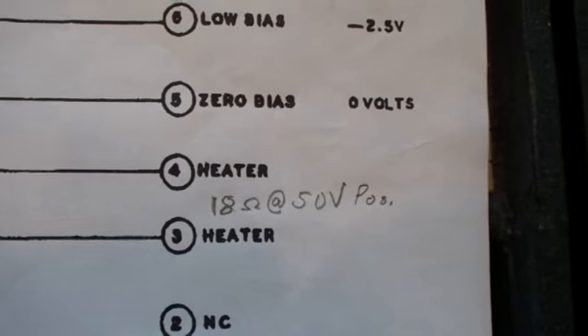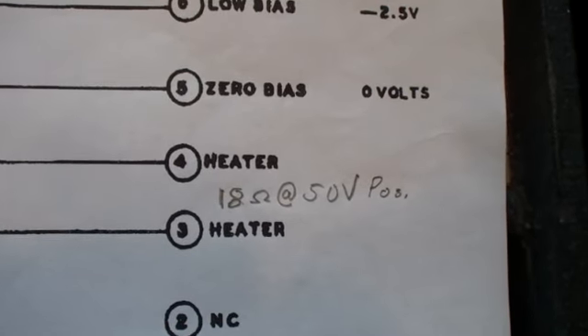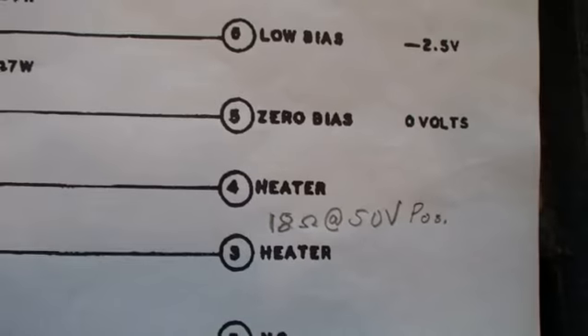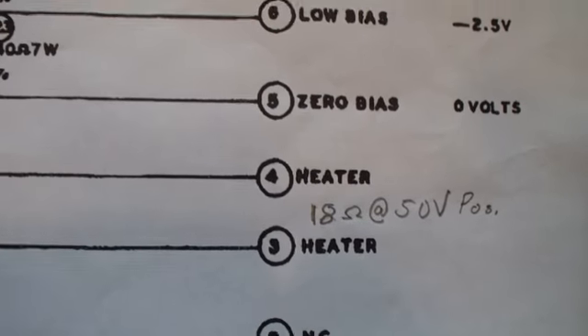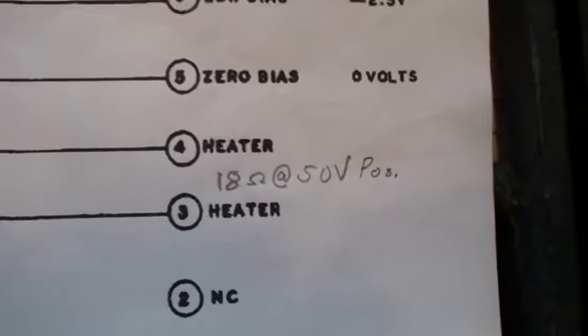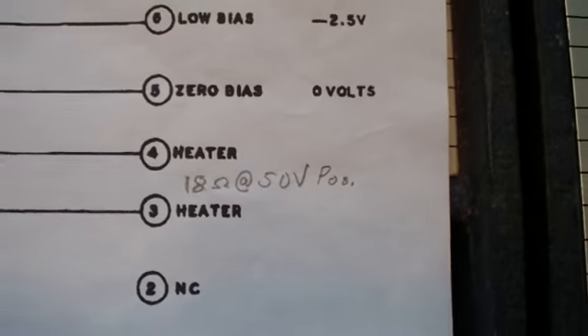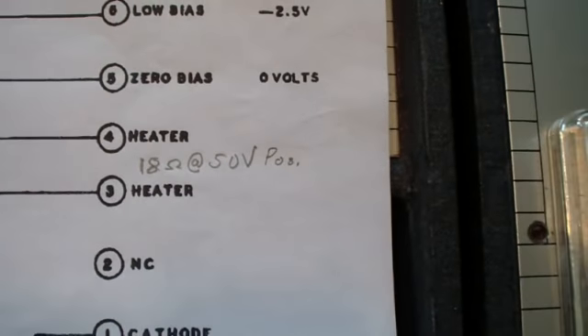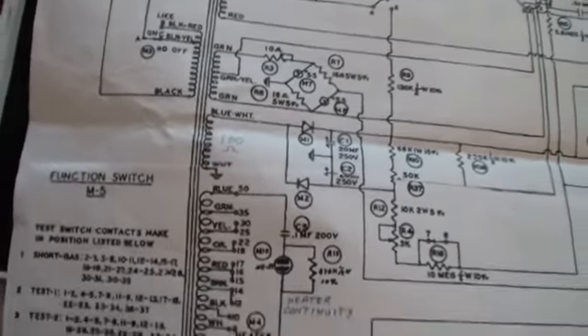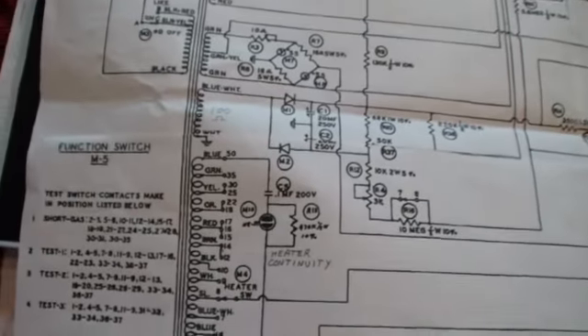By the way, if you set the heater switch to the 50 volt position and with the unit unplugged, you test across the heater connections, you should get about 18 to 20 ohms. If that's there, you know that the entire heater winding is good. Now, there might still be some problems with an individual selection, but at least the winding is continuous from bottom to top.